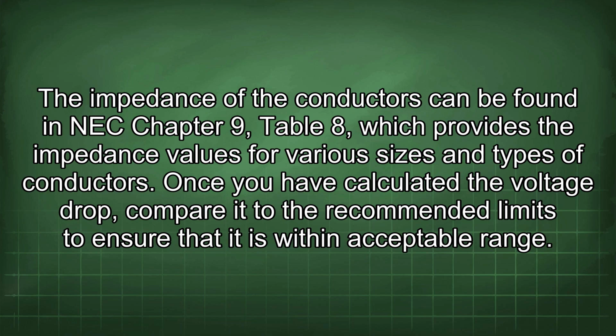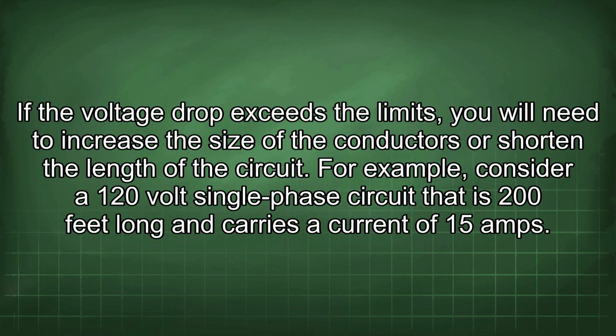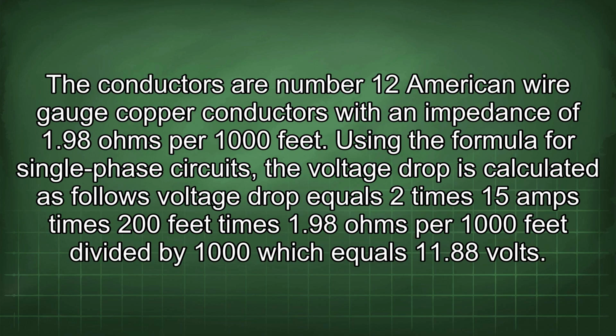Once you have calculated the voltage drop, compare it to the recommended limits to ensure that it is within acceptable range. If the voltage drop exceeds the limits, you will need to increase the size of the conductors or shorten the length of the circuit. For example, consider a 120-volt single-phase circuit that is 200 feet long and carries a current of 15 amps. The conductors are number 12 American wire gauge copper conductors with an impedance of 1.98 ohms per 1000 feet. Using the formula for single-phase circuits, the voltage drop is calculated as follows: voltage drop equals 2 times 15 amps times 200 feet times 1.98 ohms per 1000 feet divided by 1000, which equals 11.88 volts.